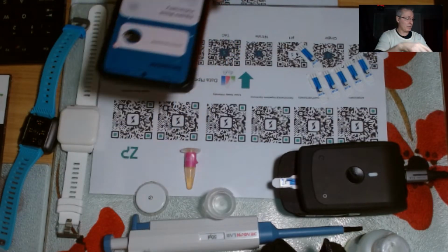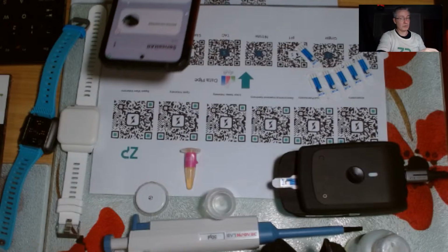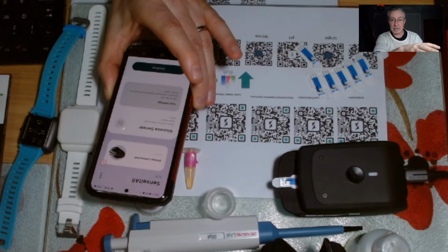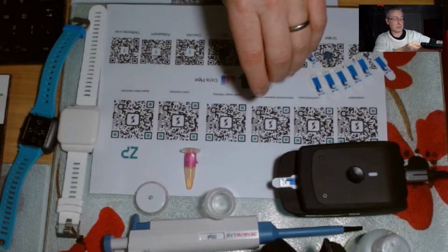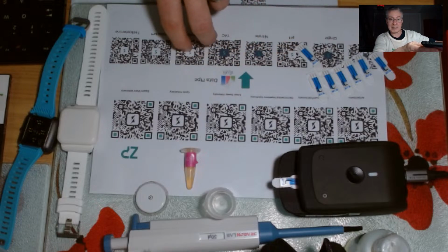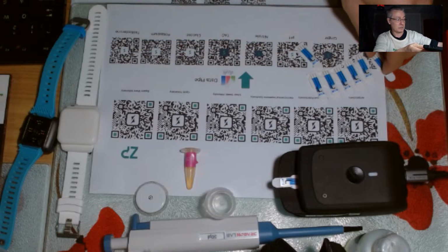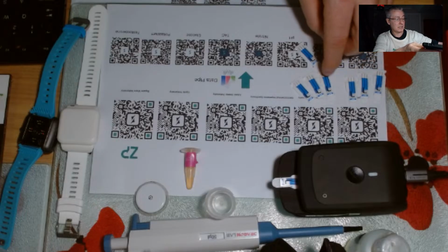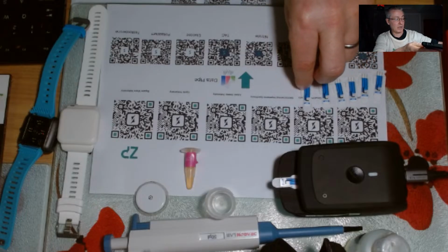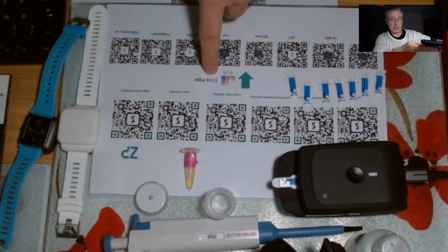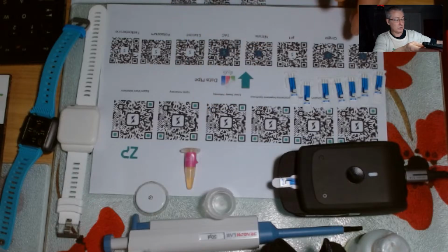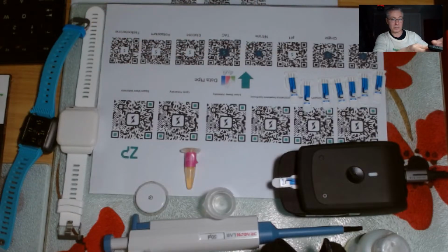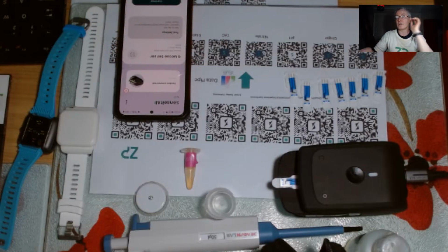But you can then get sophisticated. At ZP we have a glucose sensor. People are not just able to do scientific experiments. They can actually use our data pipe and start making assay specific QR codes. What we're trying to create is the idea that you've done all your method development, you've got your calibration curve. If you put your calibration factors in our cloud, you can then turn your raw signal into something meaningful: pH, nitrate, glucose, potassium. Testosterone is also in here. You're not limited by this list. You can create your own QR codes.